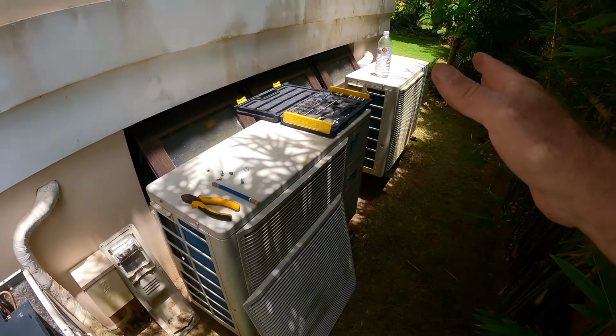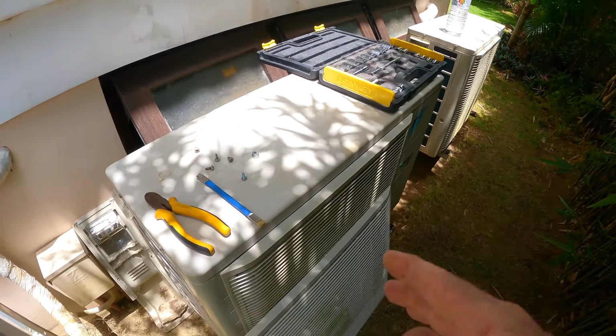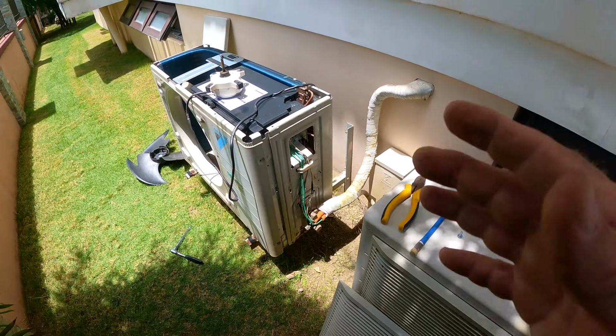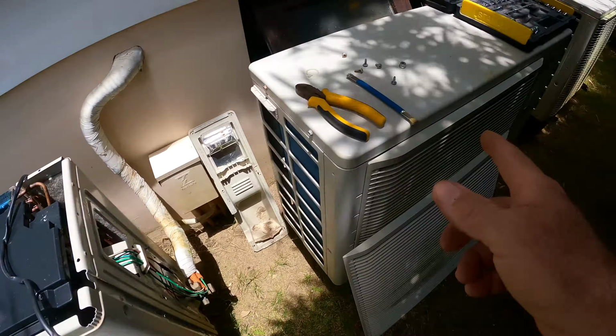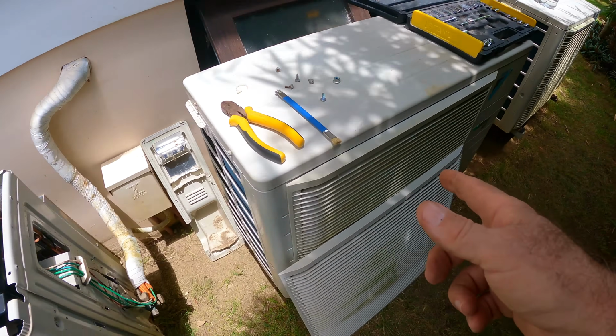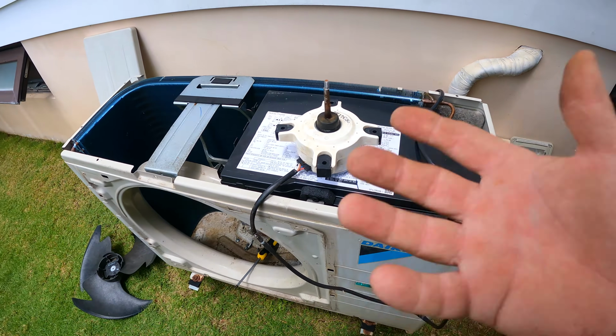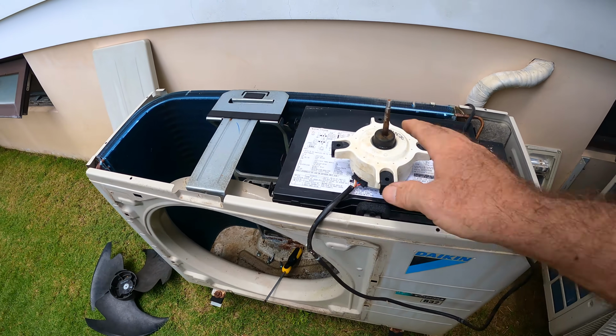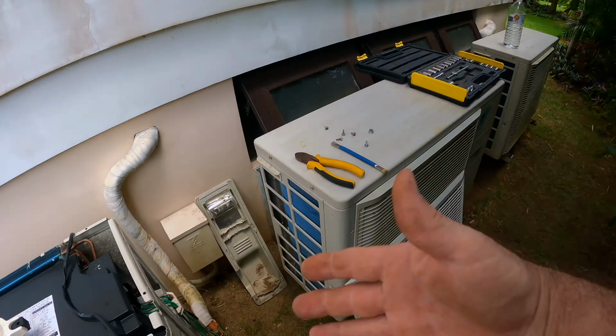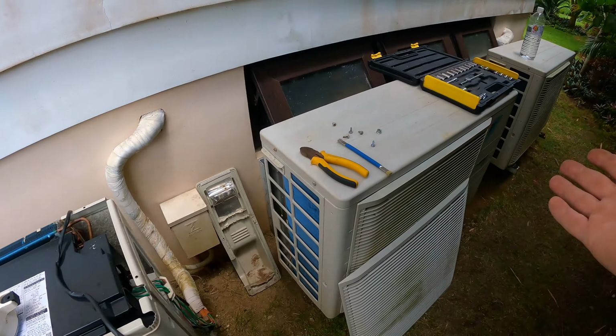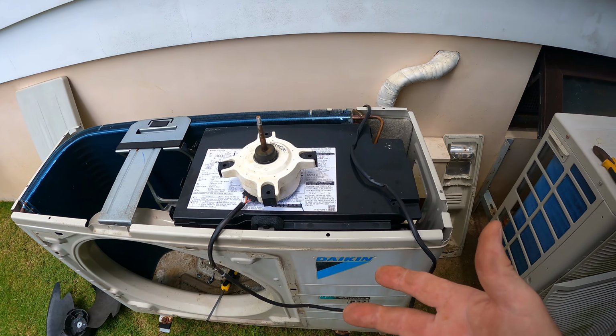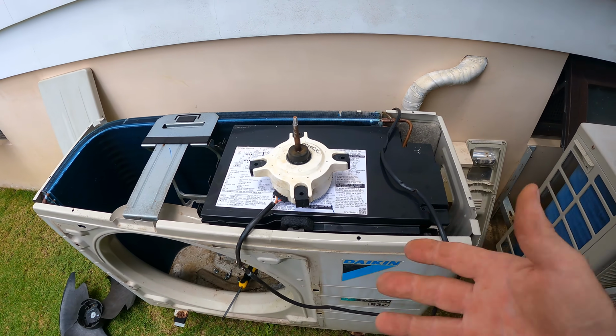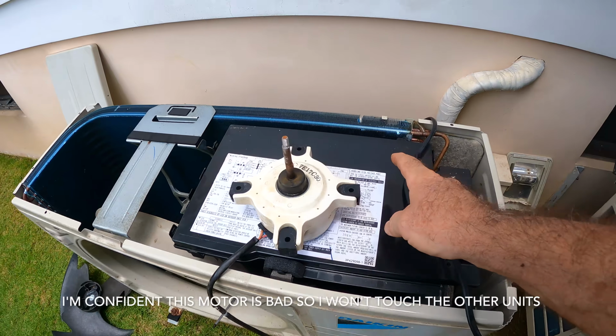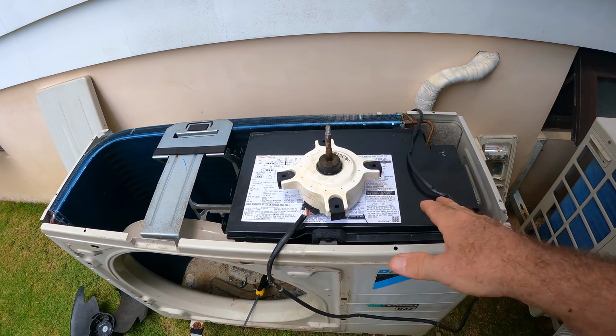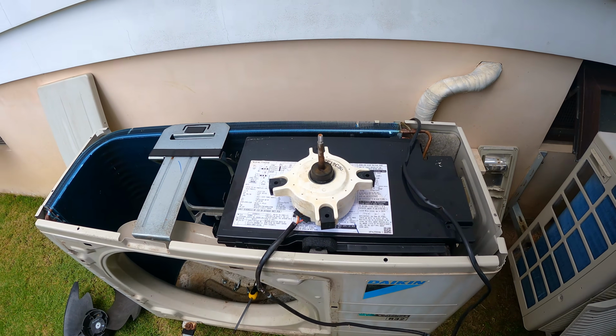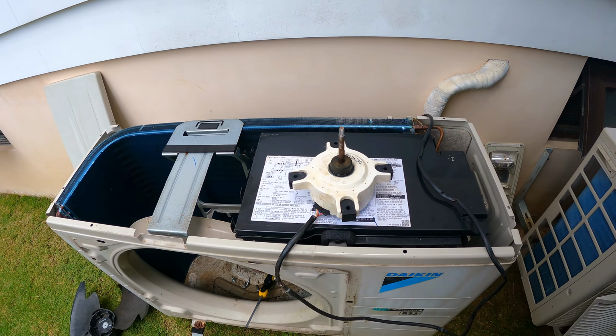Now I have the option. I have 3 condenser units out here. To validate that this is actually the problem, I could pull the motor out of one of these other 2 right here and swap it over here, and if this comes back into operational mode again, then I know that it'll be an easy fix for the one that I replace it from, depending on which one I want to keep operational until the replacement motor comes in. It will validate that this is definitely the only problem and I don't have any problem with the circuit board assembly. I'm still not sure that there's a problem with that, but it's possible, and we can test that out by just swapping out the motor.